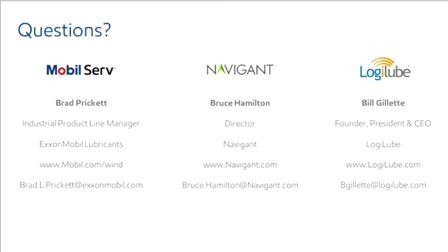And so when we go through a complete commissioning process with the operator to determine what these values are, then not only the live dashboard data is set with these thresholds, but also, and just as importantly, with the third-party labs. Remember, we're not a lab company, but we would work with the client's lab, and the data is actually pushed via an API from the lab to the dashboard. But those upper and lower threshold limits and condemning limits would be then fed into the lab's software, so that the requisite alarms are built into the system.